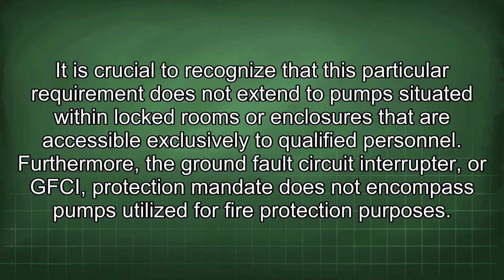It is crucial to recognize that this particular requirement does not extend to pumps situated within locked rooms or enclosures that are accessible exclusively to qualified personnel. Furthermore, the GFCI protection mandate does not encompass pumps utilized for fire protection purposes.